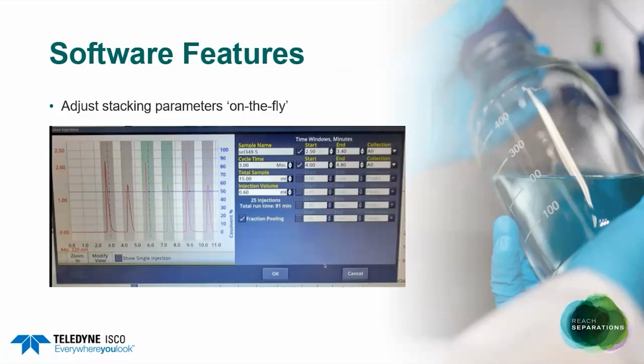We move on to some of the software features. It's very difficult to discuss all of the features of the software in this setting. It's much better to be in front of the unit, but we'll do the best we can. One feature I would like to highlight is when performing stacked injections, there is the option of being able to adjust many of the stacking parameters on the fly. What this means is you don't necessarily have to completely develop a process using single injections before you're setting up your stack, and you can almost develop your process on the fly, thereby saving some valuable time, valuable solvent, etc.